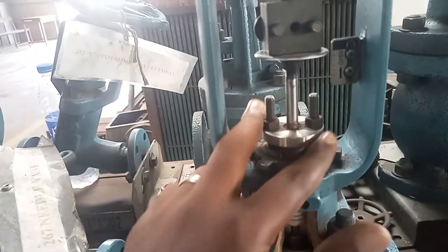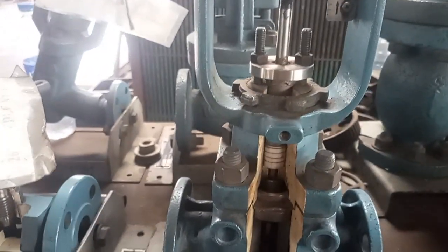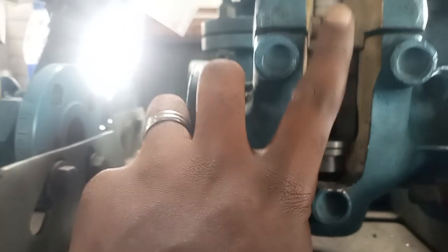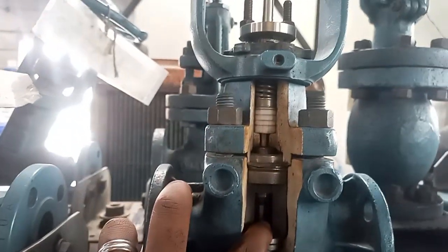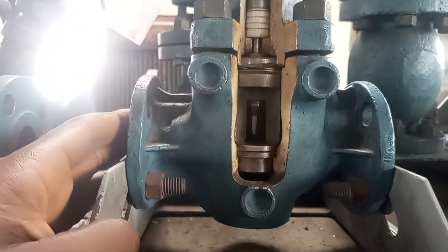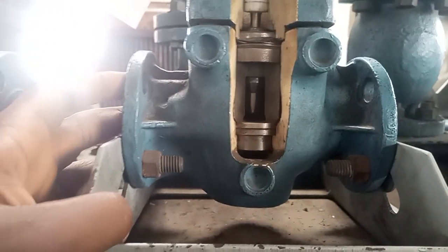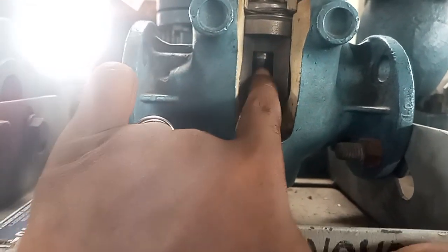Again, you have this as your gland packing, and then you have this as the valve body. So you can see that it's a special type of globe valve. This is the body, but you can see the convoluted nature and every single paraphernalia that is surrounding the valve disc. Even when this valve is fully open, it offers a reasonable, very, very high pressure drop. You can see the valve disc itself. You can see where it terminates.